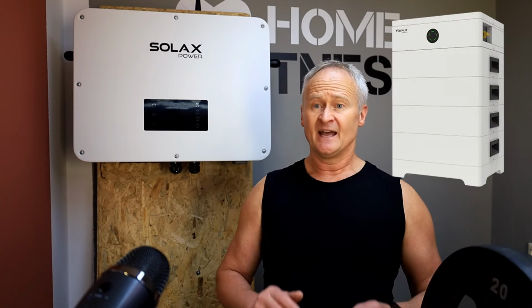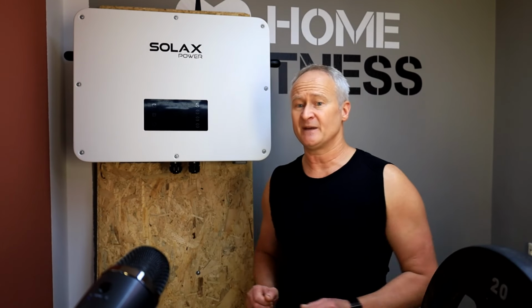Furthermore, with the Solax X3 Ultra, we have the convenient option to connect 2 separate battery strings to the device. Just like the X3 G4 hybrid inverter, it readily accepts 180 to 800 volts at its battery terminals and also offers a charging-discharging power of, in quotes, only 30 amps, but that's per individual connection. In this regard, I have to honestly admit that at first I didn't understand why the new battery, the 3.6 high voltage battery from Solax, can handle 35 and even up to 50 amps of charging-discharging current for short periods. You can't really take full advantage of this current with any Solax X3 hybrid inverter over a single battery connection. More than 30 amps are neither being drawn from the battery nor being charged into the battery. That is definitely more than enough for this particular application.